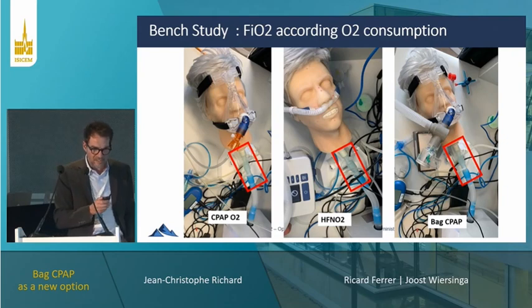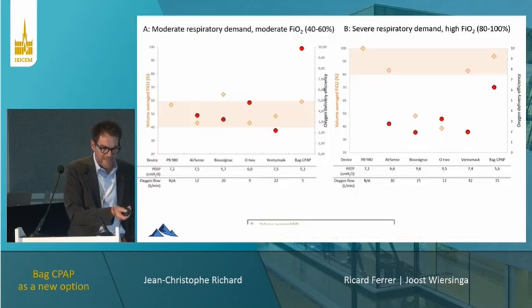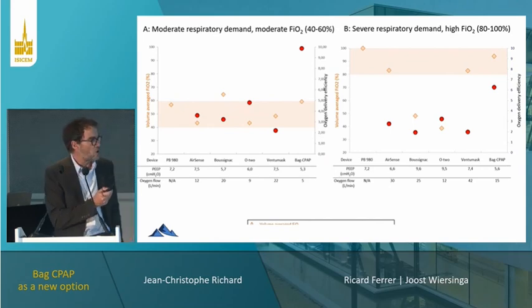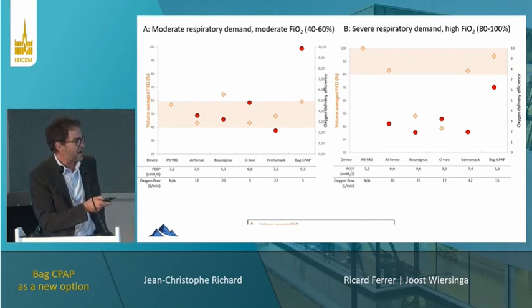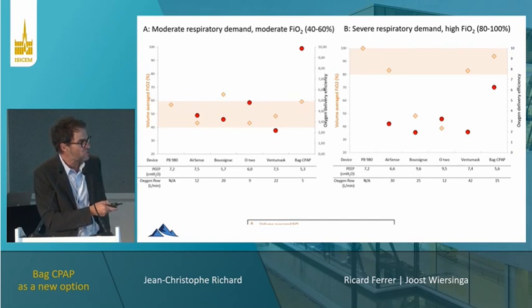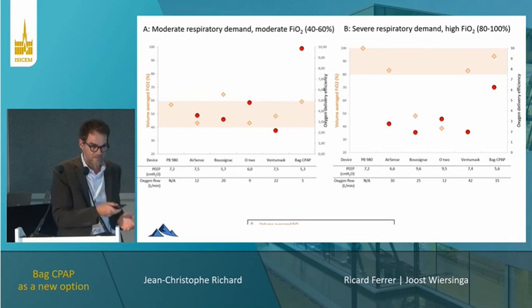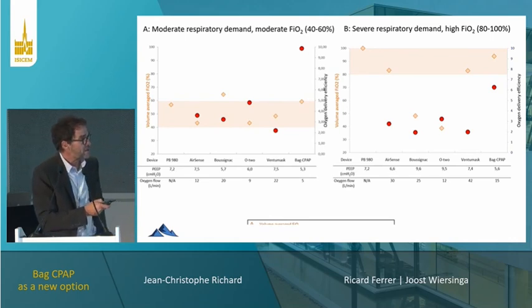We measure several systems with this specific setting, with a very realistic mannequin head, and we try to compare different devices. We compare to an ICU ventilator just as a gold standard, and we compare different systems. This is a two open valve, another system which is a Venturi mask with a Venturi, and the bag CPAP on the right.